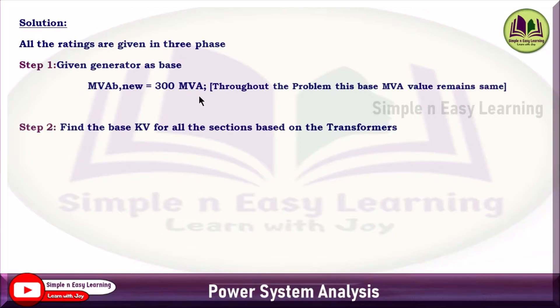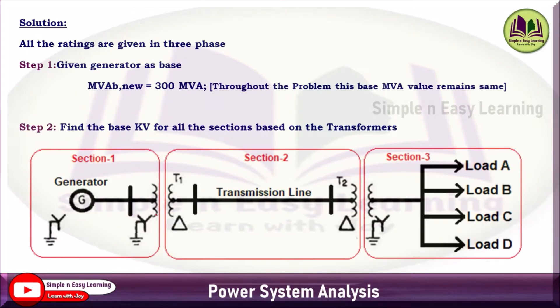Step 2: Find the base kV for all sections based on the transformer. Wherever a transformer appears, divide the circuit into HT and LT sides and find the base kV in each section. The primary side of transformer 1 is Section 1; the HT side of transformer 1 and HT side of transformer 2 form Section 2; the LT side of transformer 2 is Section 3.